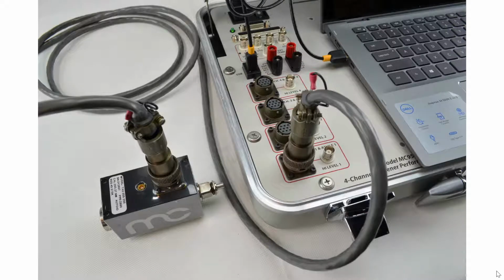Now I'm going to show you how to connect the torque angle transducer and load cell to the MC950. In this picture, what you see is the torque angle plus ultrasonic transducer, which is connected through this 10 pin connector to the MC950. These are twist and lock type connectors. This is all you have to do to connect the torque angle to the MC950.